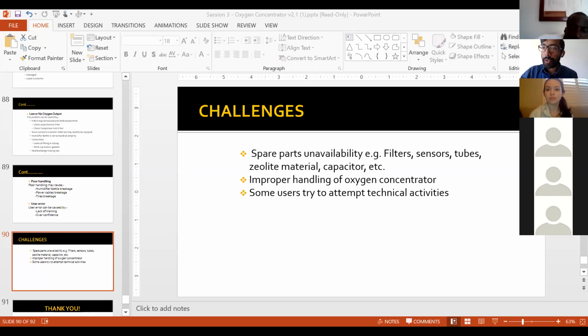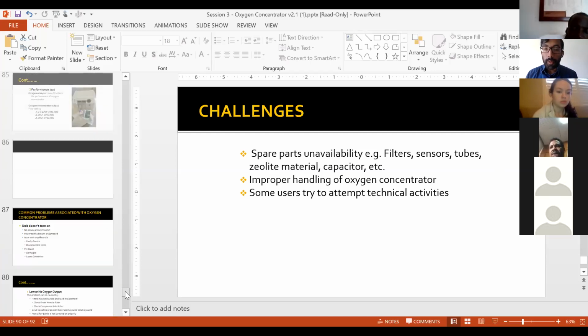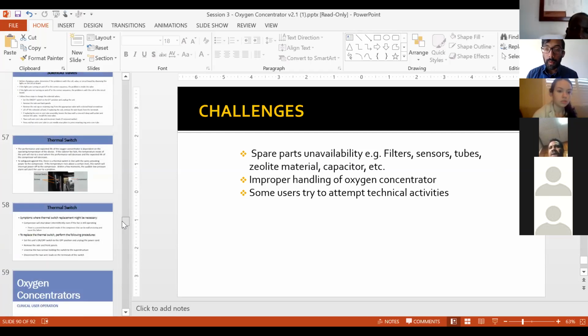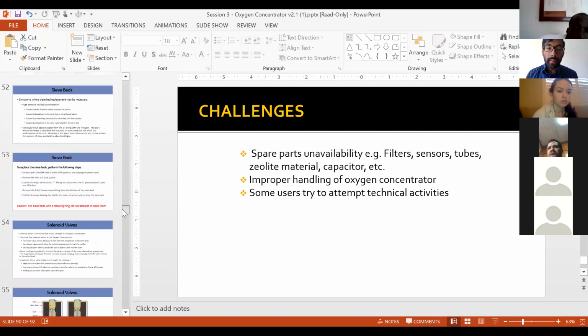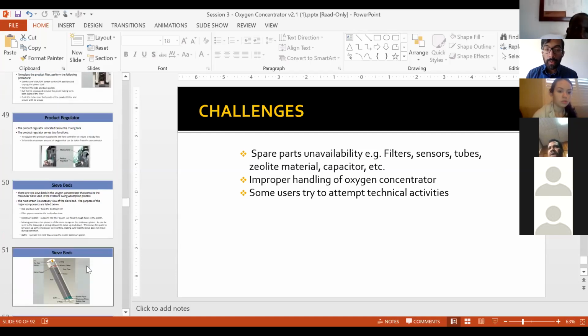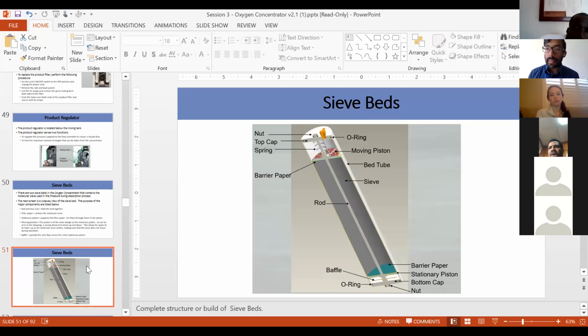Evilius is an engineer joining us from Kagera region in Tanzania. And Guna, he's asking that when you replace sieve beds of different sizes, will it cause an issue with producing oxygen on a particular model, and issues such as low oxygen alarms staying on for a while because you've replaced the wrong size sieve bed on an oxygen concentrator?